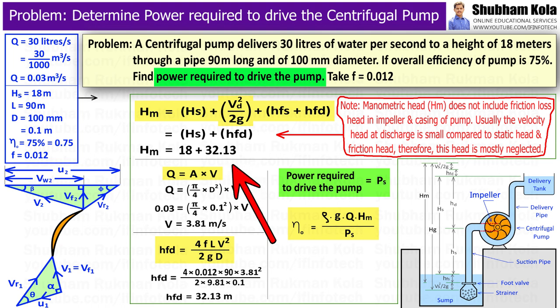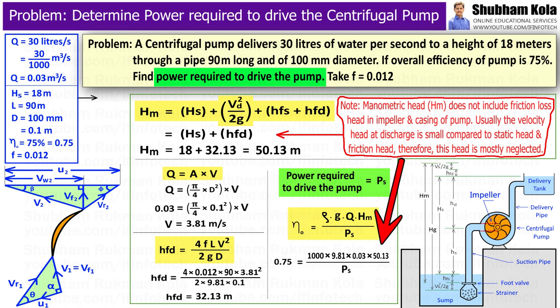And with this calculated value of hf, the manometric head Hm we got as 50.13 metre. Therefore, by putting this value in overall efficiency equation, we will calculate power required to drive the centrifugal pump as 19.67 kW.